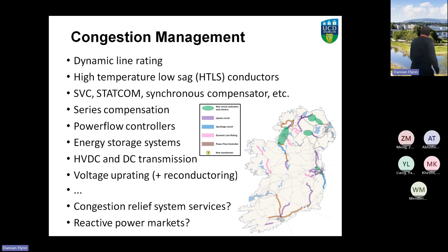If you're not familiar with dynamic line rating, typically an overhead line will have a rating based on assumptions about ambient temperature and wind speed, and so on. Those tend to be designed for worst case conditions, so the line rating will never normally be exceeded. What you might do is have seasonal ratings, so during summertime it's going to be warmer, so my line rating is going to be lower.